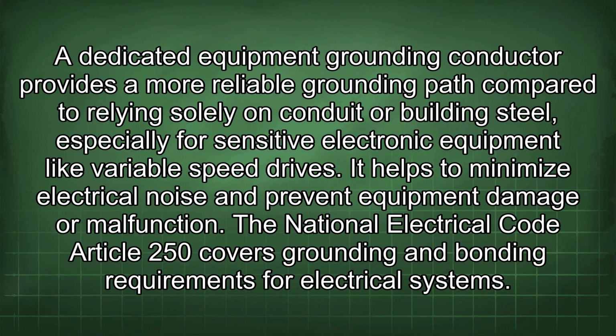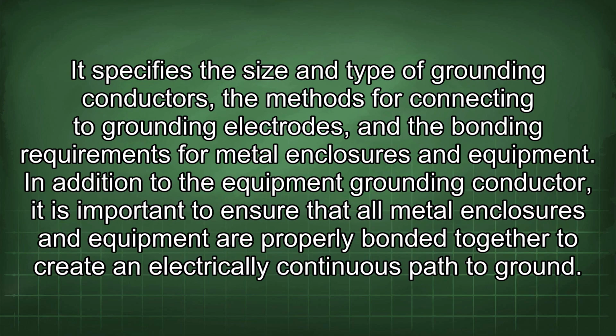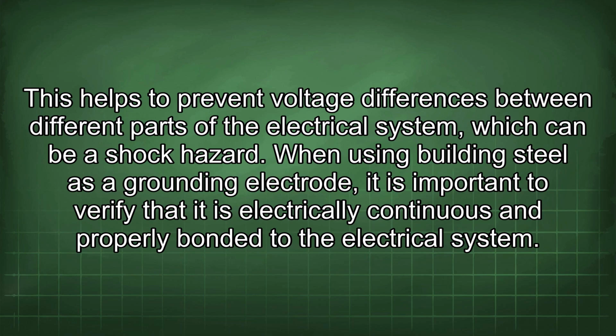The National Electrical Code Article 250 covers grounding and bonding requirements for electrical systems. It specifies the size and type of grounding conductors, the methods for connecting to grounding electrodes, and the bonding requirements for metal enclosures and equipment. In addition to the equipment grounding conductor, it is important to ensure that all metal enclosures and equipment are properly bonded together to create an electrically continuous path to ground. This helps to prevent voltage differences between different parts of the electrical system, which can be a shock hazard.